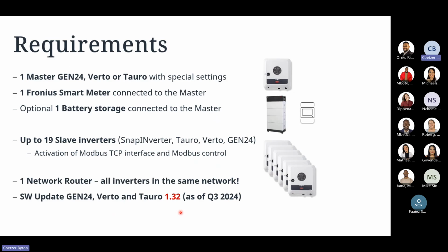So again, it's just a simple requirement when you are making use of the SPC or system power control is to have one master in the system. So it'll either be the Gen24, Verto, or Tauro. Again, with special settings. So if, for example, the Gen24 has the battery, it becomes the master and overrides the Verto or Tauro in the system. We need to make sure that we have one Fronius smart meter always connected in the system. And again, mentioning about the one battery storage connected is then the master itself.